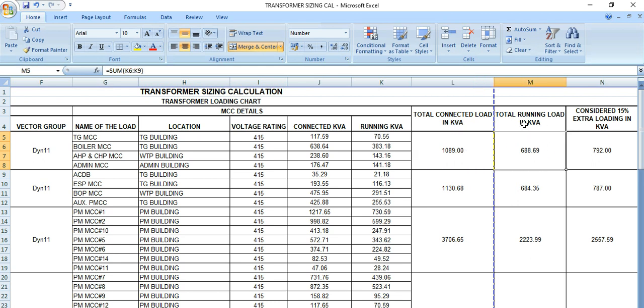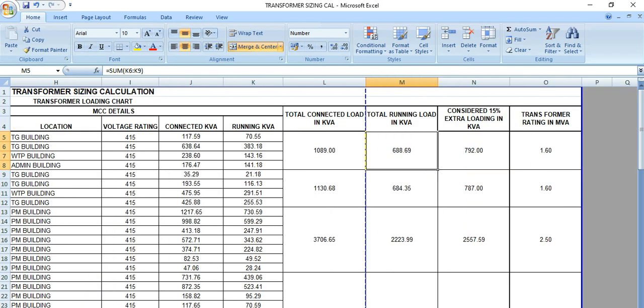These are the total running loads, which is almost 700 kVA. One thing we need to keep in mind is that this transformer is such an equipment we need to consider the margin, 15 percent or 25 percent margin during the design stage, because in future there may come some additional loads.